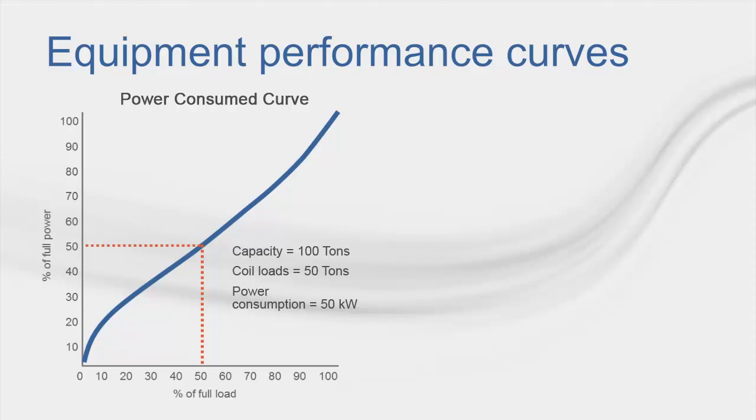The story doesn't end here, though. The power consume curve is created using equipment data generated by holding the condenser entering water or air temperature constant and unloading it on the evaporator side. We still need to take into account the ambient modification expected for the given hour, based on the associated weather data.